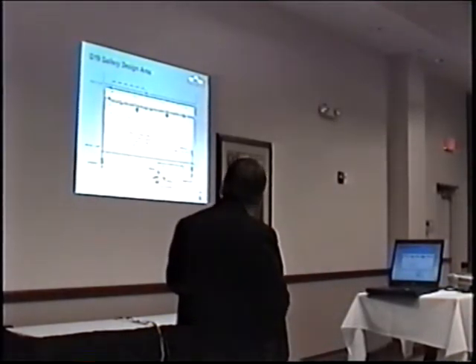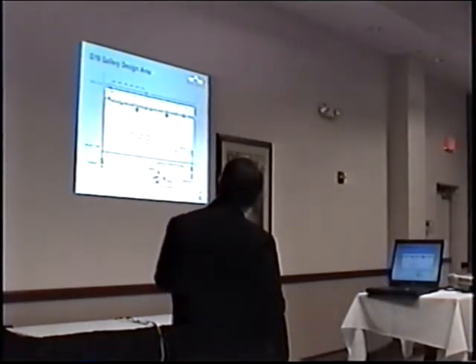Piping system, a shut-off valve, a deluge valve. This had to be a pre-action system, so this was a special valve that could have low pressure on one side, high pressure on the other, and then release. Basically, an empty piping system.